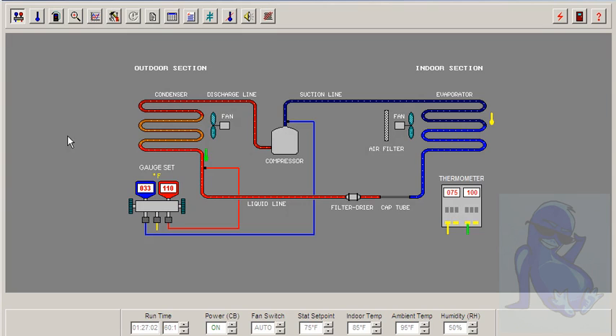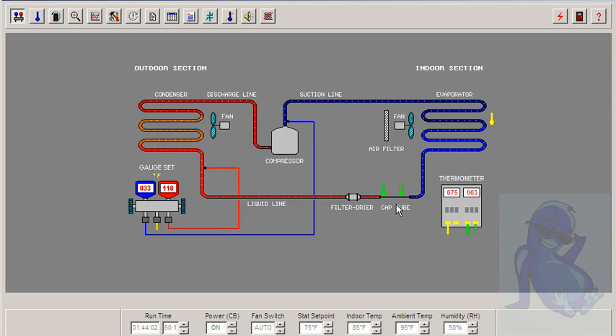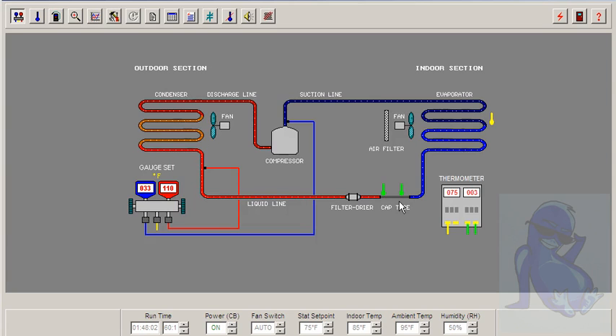And let's take a reading across the metering device. Cap tube differential. Look at that. We have a 3 degree difference on our cap tube. So we have an issue.